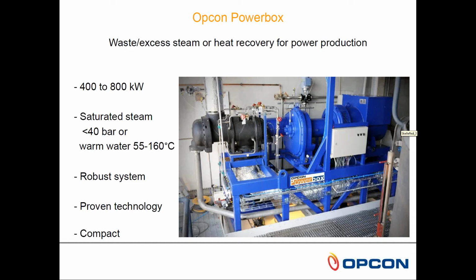And the most simple setup for this is to utilize saturated steam. And that's very unique. You don't use saturated steam in a conventional turbine. There you need to have superheated, absolutely dry steam to make it work. But here we can use very simple saturated steam, up to 80% water within the steam. And that's because of our double screw turbine. We can use up to 40 bars pressure on this one.